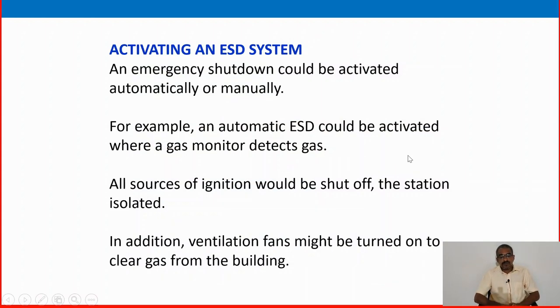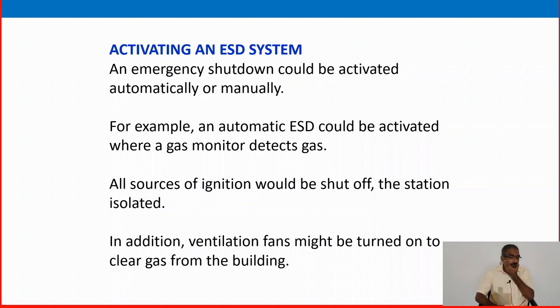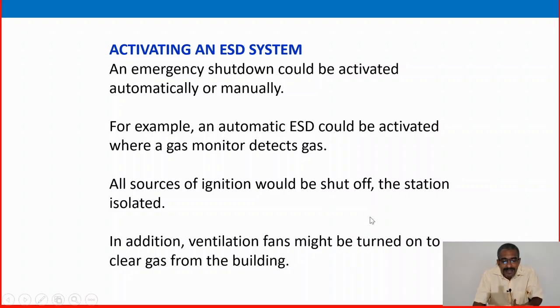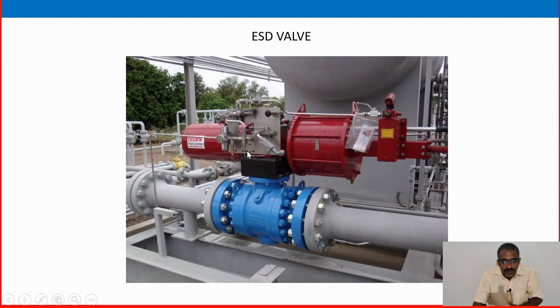Activating an ESD system: an emergency shutdown could be activated automatically or manually. Automatically means — if you remember the trip system video — the trip system is activated in any case, for example, separator level high-high or pressure switch high-high in the separator. So automatically, the ESD valve will close.